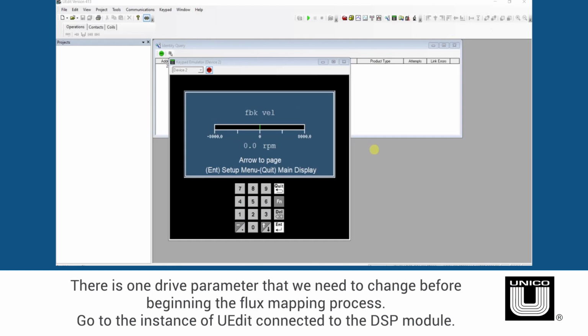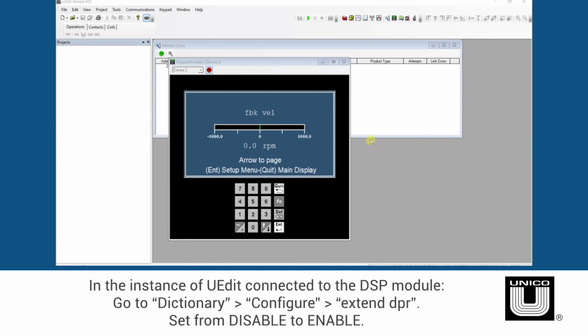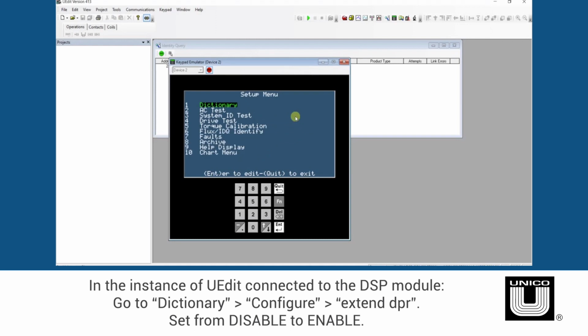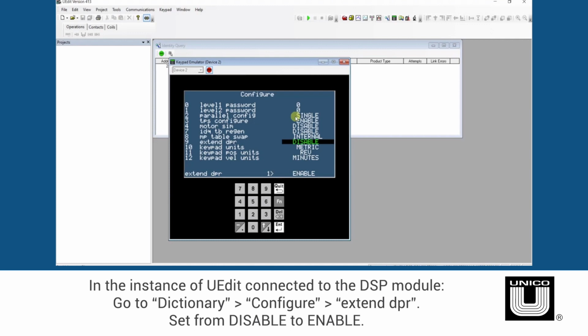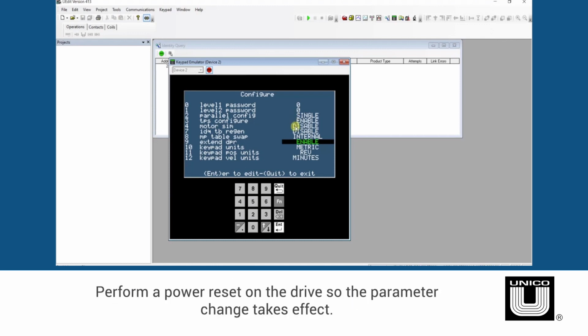There is one drive parameter that we need to change before beginning the flux mapping process. So go to the instance of UEdit connected to the DSP module. Go to Dictionary, Configure, and set Extend DPR from Disable to Enable. This adds additional functionality in the drive for obtaining accurate estimates of the D-axis and Q-axis inductance, which I will discuss later. Then perform a power reset on the drive so the parameter change takes effect.